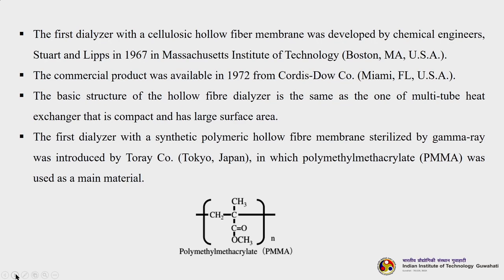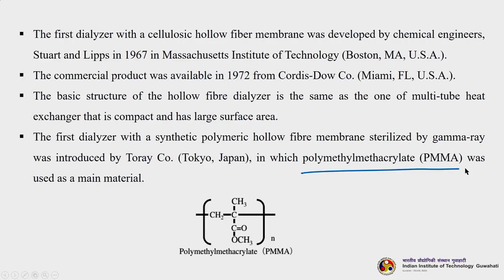The first dialyser with a cellulose hollow fibre membrane was developed by chemical engineers Stuart and Lipps in 1967 at MIT in Boston. The commercial product was available in 1972 from Cordis Dow Company in Miami. The basic structure of the hollow fibre dialyser is the same as a multi-tube heat exchanger — compact with a large surface area. The first dialyser with a synthetic polymeric hollow fibre membrane sterilized by gamma ray was introduced by Toray Corporation in Japan, using polymethyl methacrylate (PMMA) as the main material.